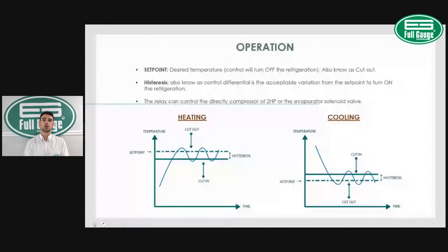Operation. So controllers work based on set point and differential. Set point is the cutout temperature, and the differential is the cut-in temperature. So if we set the controller for cooling, whenever the differential is reached, the compressor will go on and try to bring the temperature down until it reaches the set point. When the temperature reaches the set point, the compressor will go off and the temperature starts to rise again. Whenever it reaches the differential, it brings the compressor back on. That's under the cooling mode.